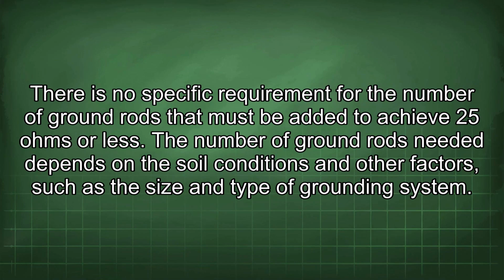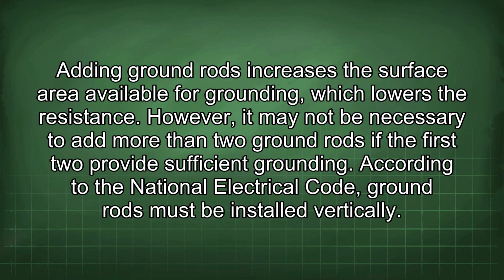There is no specific requirement for the number of ground rods that must be added to achieve 25 ohms or less. The number of ground rods needed depends on the soil conditions and other factors such as the size and type of grounding system. Adding ground rods increases the surface area available for grounding, which lowers the resistance. However, it may not be necessary to add more than 2 ground rods if the first 2 provide sufficient grounding.